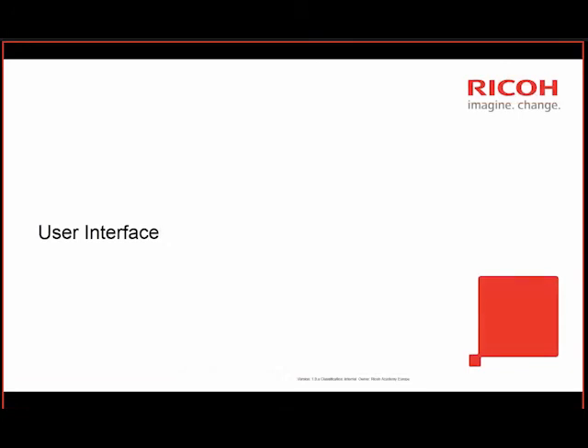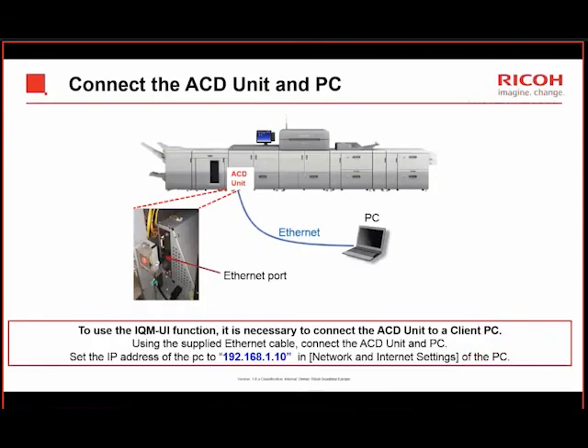The user interface, we'll talk about this a bit because this is new for the 9200 Plus. So you have your ACD unit, still the same. You will recognize this if you have seen the 9200. It's the old pyramid system. It's exactly the same. But now, part of your installation procedure is you need to have a PC, and it needs to be directly connected to the back of the pyramid system. There's an Ethernet port in the back. You install a PC, connect an Ethernet cable to the PC, and connect an Ethernet cable to the pyramid system.